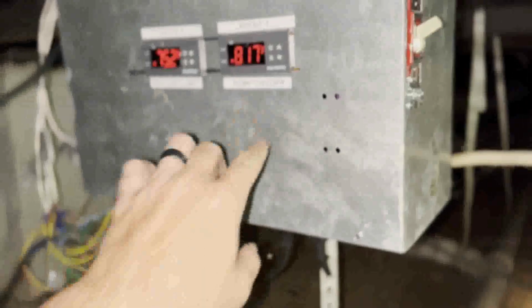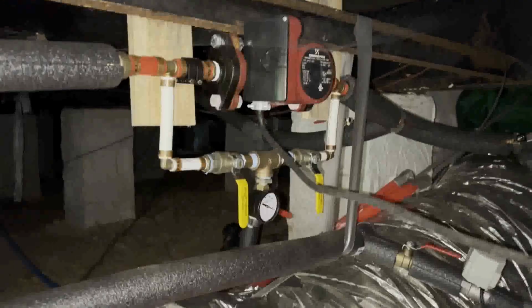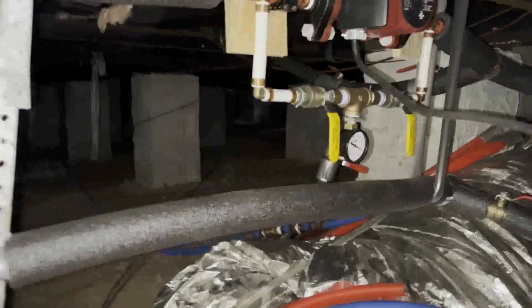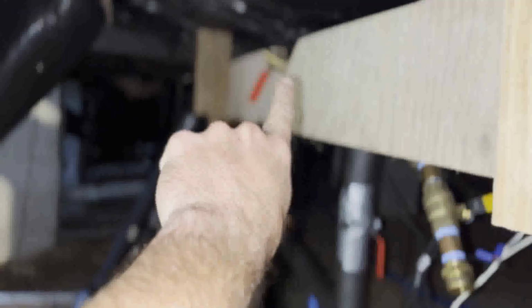Ultimately, outside the boiler, it'll get to temperature, and once it gets warm enough, it'll bring on its own pump, and that'll start moving water around the primary circuit, and that will come up under the house here. This thermostat here, once it gets so warm, will turn on the secondary pump. So I have a primary-secondary system. So there's the secondary pump. This is for build out over here. So we got some kind of future stuff you can kind of see there.